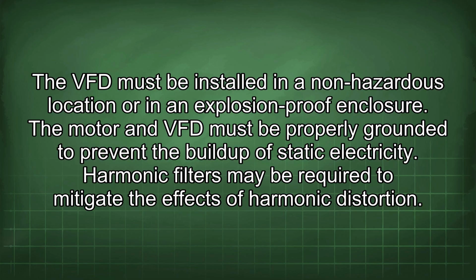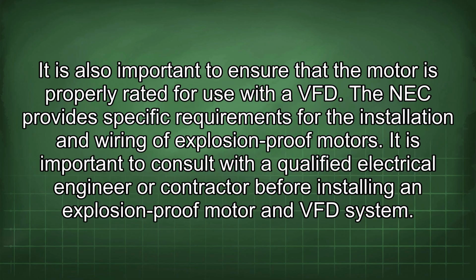The VFD must be installed in a non-hazardous location or in an explosion-proof enclosure. The motor and VFD must be properly grounded to prevent the buildup of static electricity. Harmonic filters may be required to mitigate the effects of harmonic distortion. It is also important to ensure that the motor is properly rated for use with a VFD. The NEC provides specific requirements for the installation and wiring of explosion-proof motors. It is important to consult with a qualified electrical engineer or contractor before installing an explosion-proof motor and VFD system.